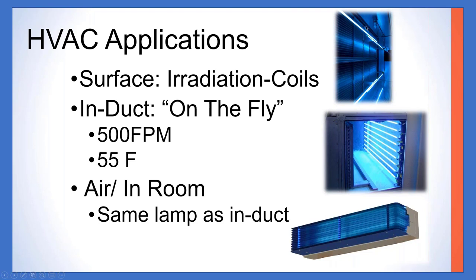Back to the coil, if I'm doing a coil irradiation, this is usually used for coil cleanings, drain pan cleaning, and general maintenance of an air handling system. That's about 7 to 10 watts, or lamp watts, per square foot.